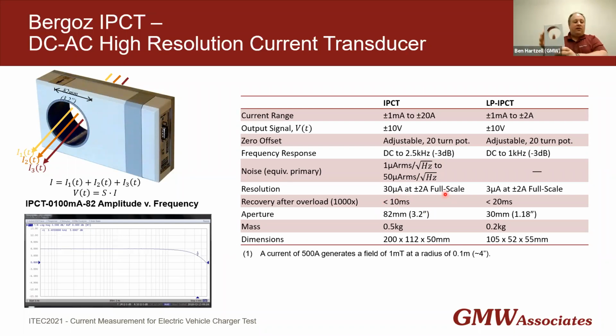And it has a very large aperture. So given that you might be measuring 2 amps, it has an 82 mm aperture, 3.2 inches, which is large enough to pass a very large cable bundle through. Here I have actually just a 3-phase charging cable. You can see it clears through no problem.